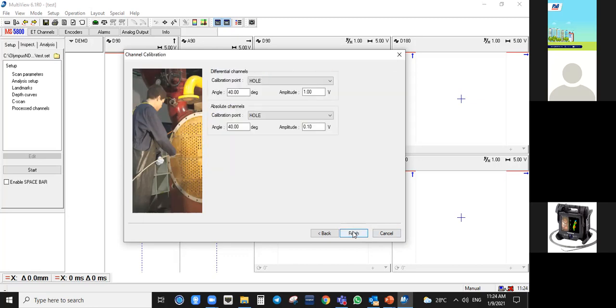Then just press next. And then here, as per ASME standard, any hole, the angle should be 40 degrees and an amplitude of 1 volt. So make sure that on the differential channel, your hole will give you a 40-degree angle and an amplitude of 1 volt, or close to 1 volt.